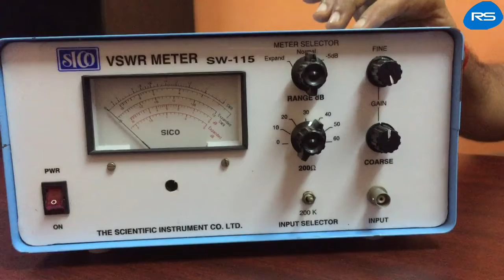This is a VSWR meter. It is used to measure voltage standing wave ratio, that is Vmax upon Vmin. Basically, a VSWR meter is a sensitive, high gain, high quality factor, low noise voltage amplifier. Input of VSWR meter is the detected signal, the output of the microwave detector. Output of the amplifier is measured with a square law calibrated voltmeter, which directly gives the VSWR reading of Vmax upon Vmin for an input of Vmin, after the meter is adjusted to unity VSWR for an input corresponding to Vmax.